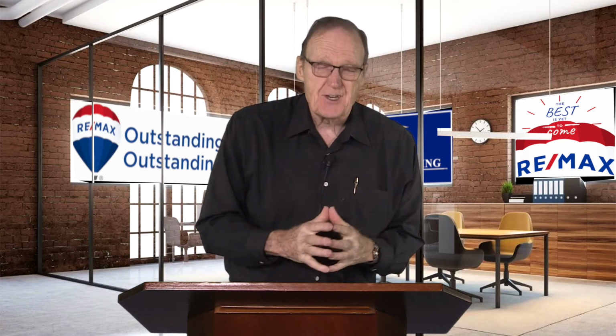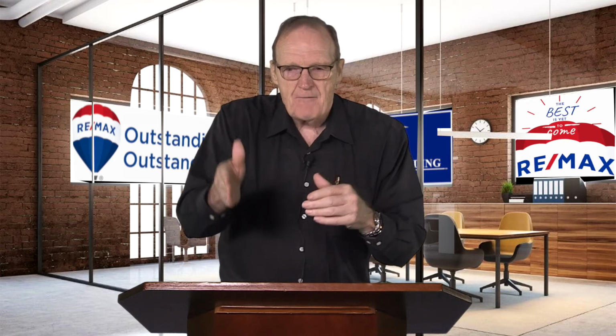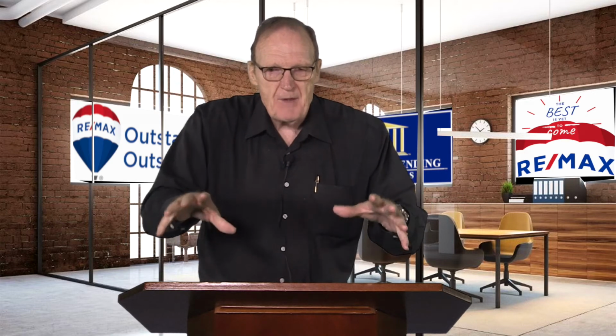You're looking at containment. And one of the tough ones is the furnace room. If the furnace room abuts up against a dwelling, if it doesn't, if it goes to a common area, it's not as critical. But if the furnace room butts up, for example, if there's an apartment right above the furnace room, or there's a basement apartment going up against the furnace room, it's critical that that furnace room be finished in fire-rated drywall or some kind of device that will withstand at least 30 minutes of burn before it burns through to the adjacent unit.